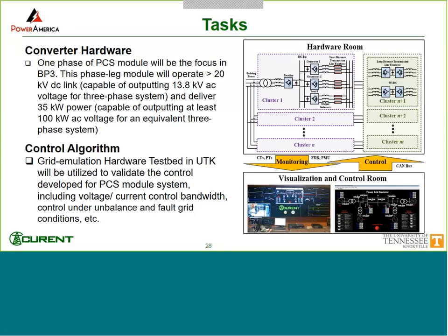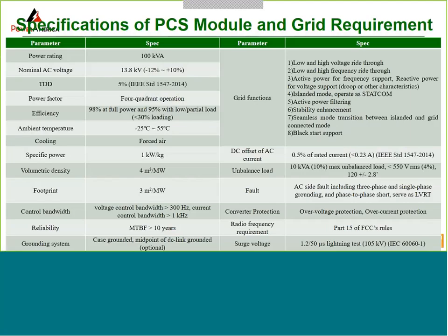system called the hardware testbed. We will be using that to develop the control for the PCS module and test all those functions. Because it's a much lower voltage, we can switch at around 20 kilohertz, which is equivalent to the higher voltage silicon carbide converters in terms of control bandwidth. And this is the spec we have for the PCS we are developing. Some of the key things are the grid-related functions, which is quite different from regular converters like a motor drive.